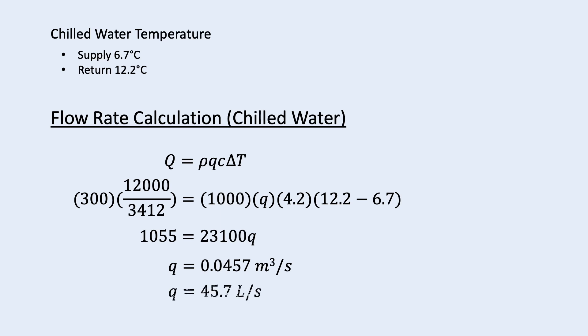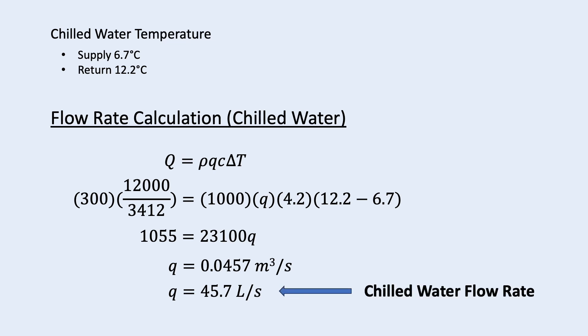So the flow rate is 0.0457 meter cube per second. Multiply this by 1000, we will convert it into 45.7 liter per second. So this is the chilled water flow rate requirement.